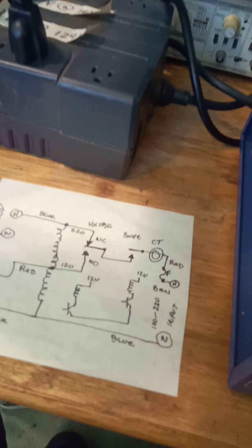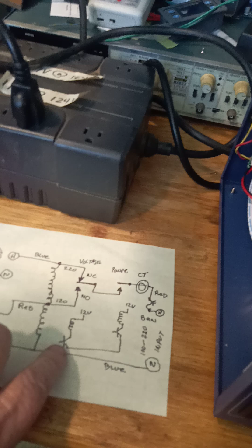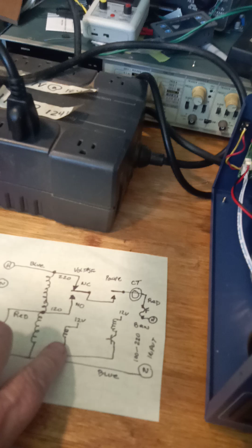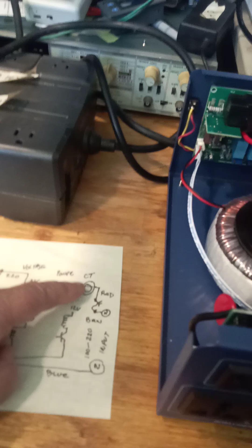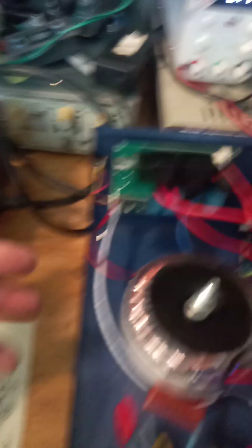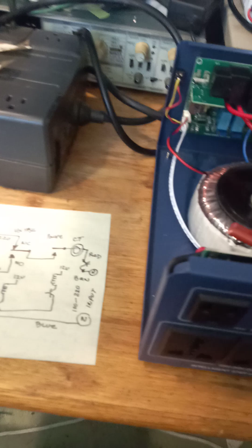That's the safest voltage, because you can put 110 into a 220 transformer, but you can't put 220 into 110. So normally it's closed naturally on the 220, and the current voltage monitor senses, and if it's 110 volts, it switches this relay on. It's pretty advanced, it has a current sense transformer and temperature sensing on the transformer to see if it's getting too hot.